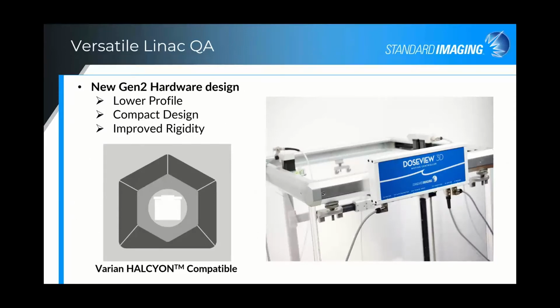The new Gen 2 second generation Doseview 3D has a lower profile, more compact design for improved rigidity throughout, but also makes it Halcyon compatible for use in the Halcyon bore for doing your QA and measurements within that system.